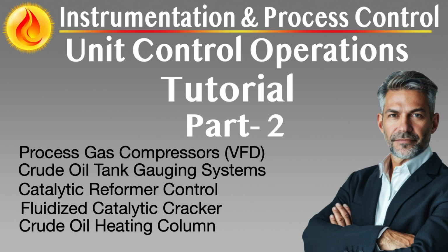In LPMP applications, where process flows and pressures are more variable, VFDs deliver high responsiveness to both planned set point changes and unplanned transients. At the heart of modern control architectures is a multi-loop strategy involving suction pressure control, discharge pressure regulation, anti-surge protection, and flow balancing. The VFD acts as the primary actuator, modulating compressor speed in response to process variable set points.